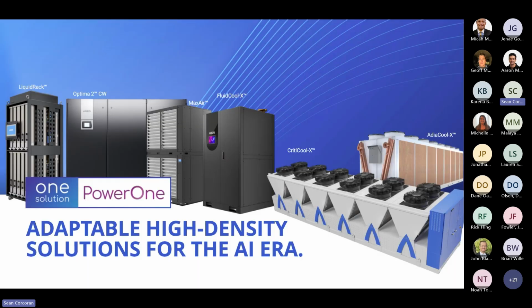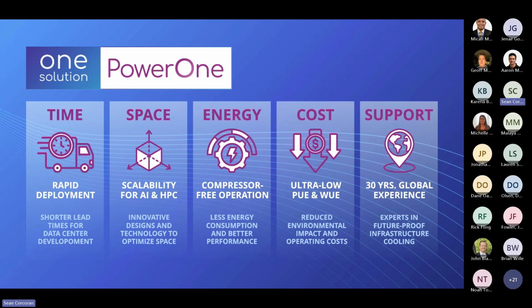So the offering, right? We have everything from a small 60 kW chilled water unit and DX unit to a large chiller, dry coolers, as well as CDUs and fan walls. And the other product, the liquid rack off to the left there, is something that I'll talk about in a few slides, which is one of the new technologies of liquid cooling. But with the PowerOne product offering, we're looking at the ability to rapidly deploy, shorter lead times, and scalability for high density, from low density to high density, with new technologies and disruptive technologies that you'll see from our liquid rack product.